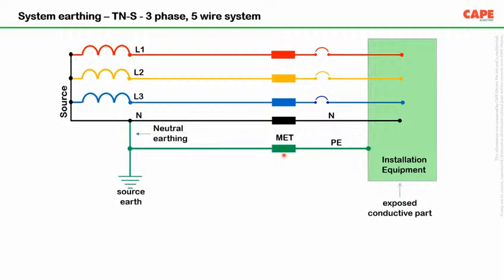The conductor is your earthing, because a fault current goes through this particular conductor to the transformer, and as a result, heavy fault current flows and the device is disconnected, the supply is disconnected. Now, for the purpose of reducing the touch voltage, for example, the equipment and the local place where you are standing, imagine you are standing on the 10th floor of a building. Why am I saying 10th floor? Because nowadays we have large buildings. Imagine you are standing at the 10th floor in front of an electrical apparatus.